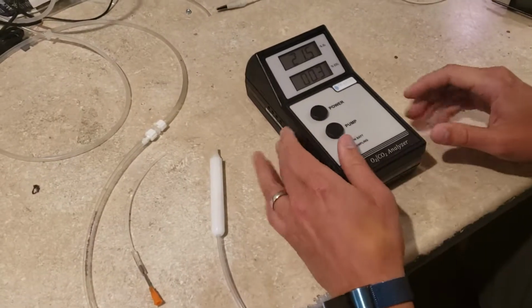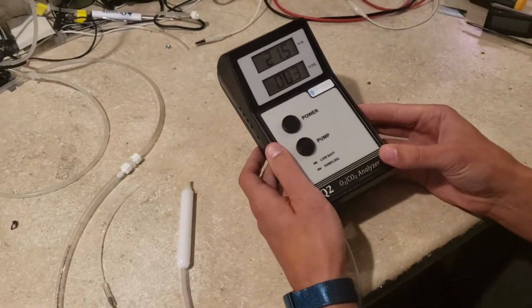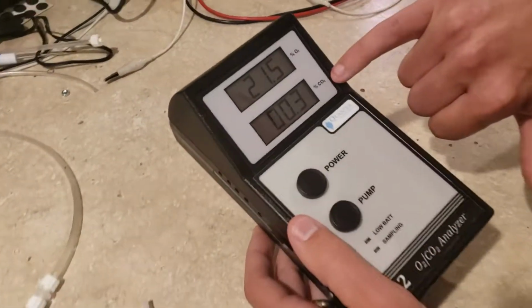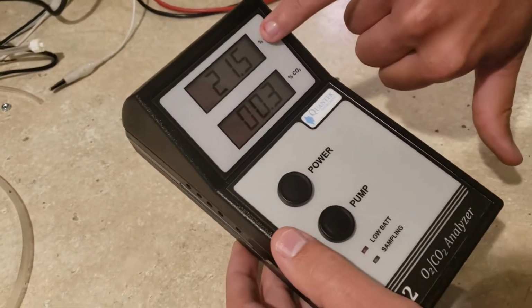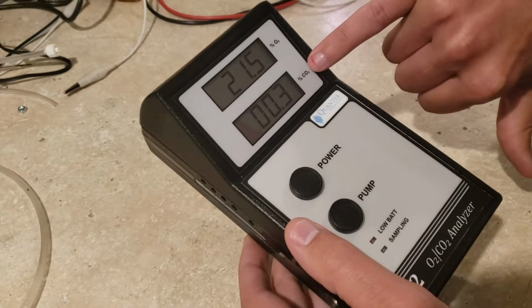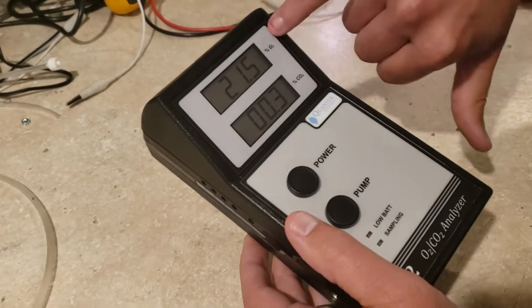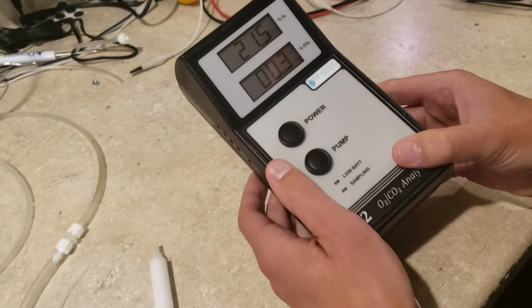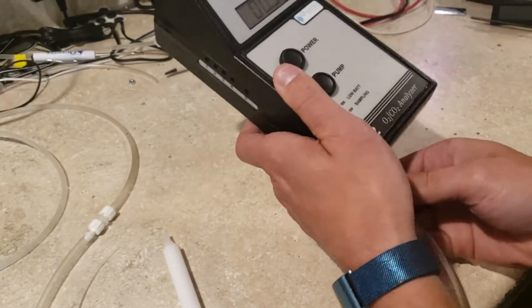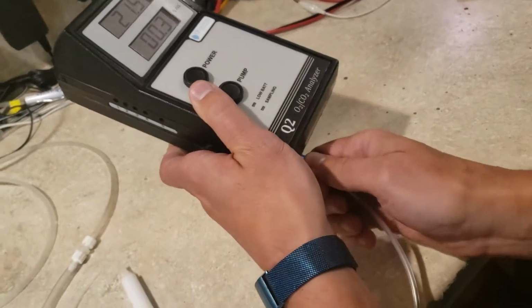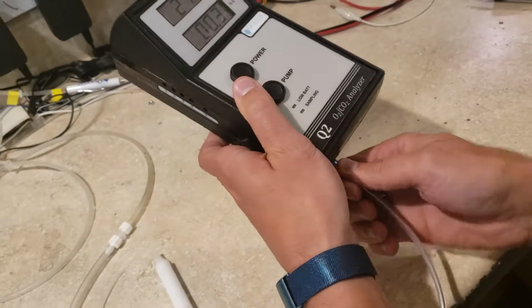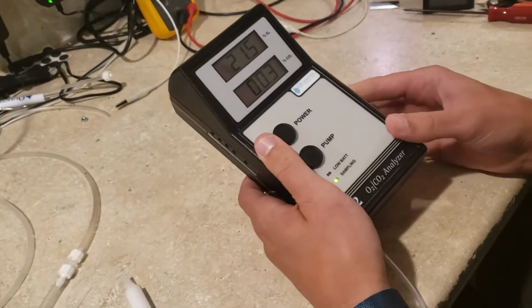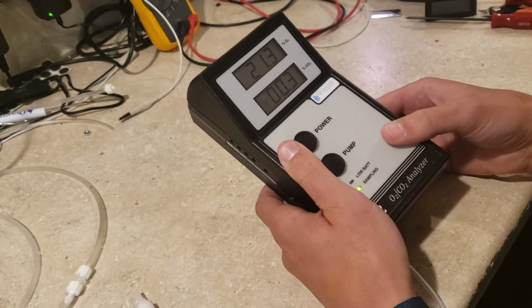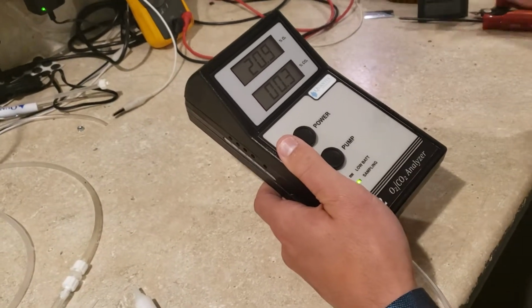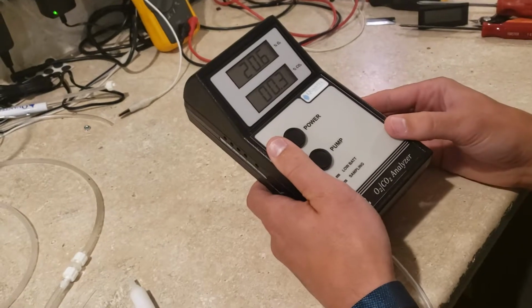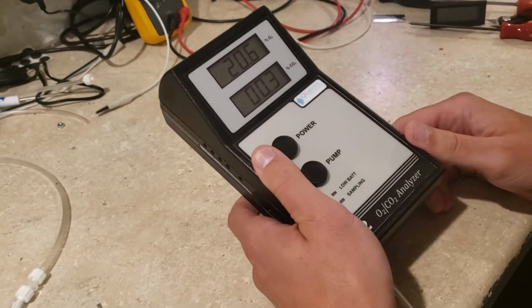Okay, so today we're going to go through the calibration procedure for a model Q2, which measures oxygen and carbon dioxide. As you can see right now, our readings are 21.5 and 0.3, which is close for room air, but not exactly where we want them to be. So the first thing we're going to do is check to make sure that the sample probe is screwed in fairly tight. It should be pretty tight with your hand, and then we're going to hit the pump button. We want to make sure that the pump time is at least 5 or 6 seconds, long enough to draw in a sample, and then we're going to watch the reading change.